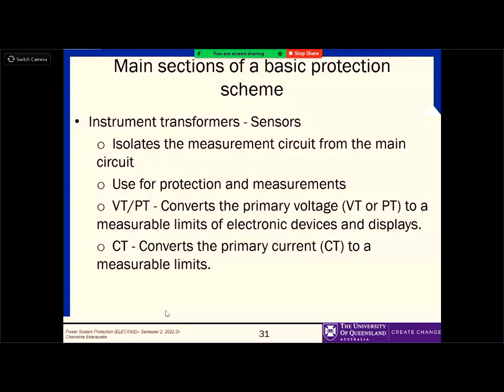CTs mean current transformers — for example, the line current might be 1500 amps, but the relay can't handle that magnitude, or it would be damaged. So you reduce the current to a couple of amps, which the relay measures to take appropriate action. The same concept applies for voltage, which is dropped from, say, 220 kV to 120 volts.